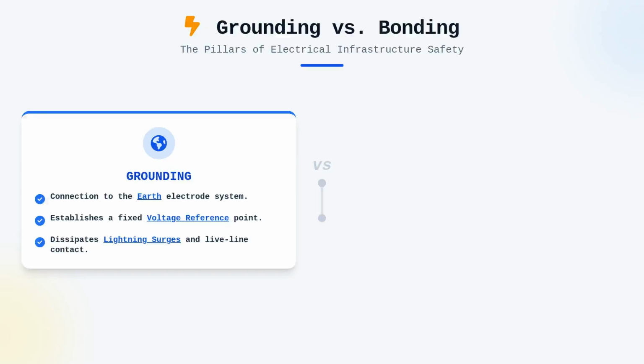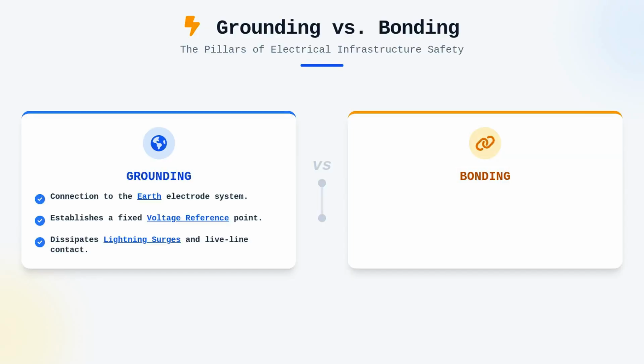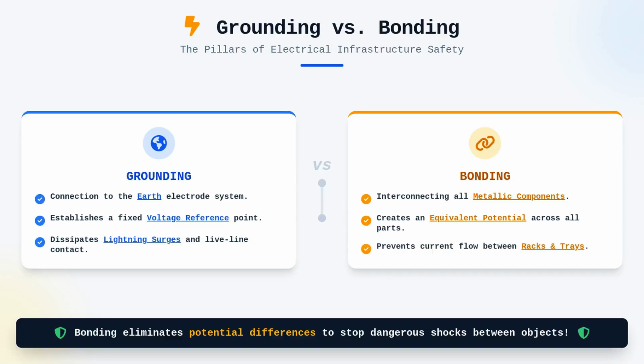Bonding, by contrast, is the process of interconnecting all metallic components in a facility to create an electrically continuous path. The goal here is not necessarily to reach an earth potential at every point, but rather to ensure that all metallic parts are at the same equivalent potential. When you interconnect racks, cable trays, and conduit, you effectively eliminate potential differences between them, which prevents the dangerous flow of current through anyone who might touch two metallic objects simultaneously.